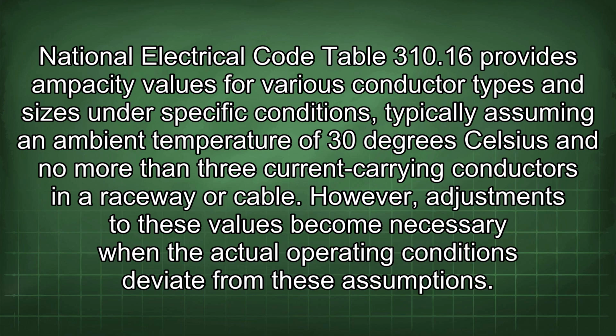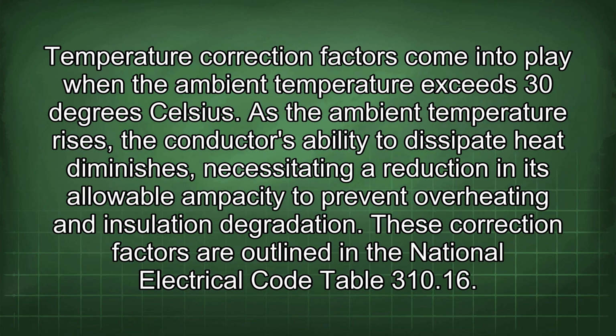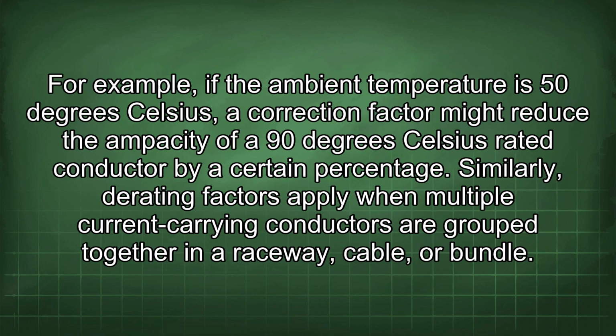However, adjustments to these values become necessary when the actual operating conditions deviate from these assumptions. Temperature correction factors come into play when the ambient temperature exceeds 30 degrees Celsius. As the ambient temperature rises, the conductor's ability to dissipate heat diminishes, necessitating a reduction in its allowable ampacity to prevent overheating and insulation degradation. These correction factors are outlined in the National Electrical Code Table 310.16. For example, if the ambient temperature is 50 degrees Celsius, a correction factor might reduce the ampacity of a 90 degrees Celsius rated conductor by a certain percentage.